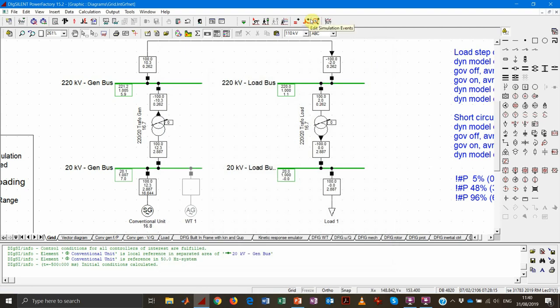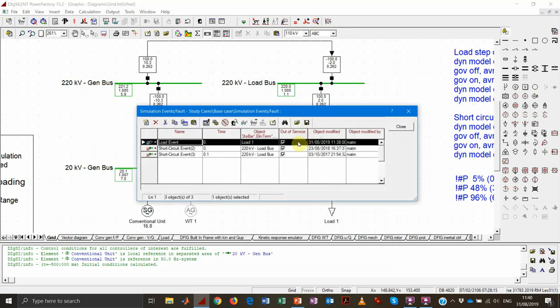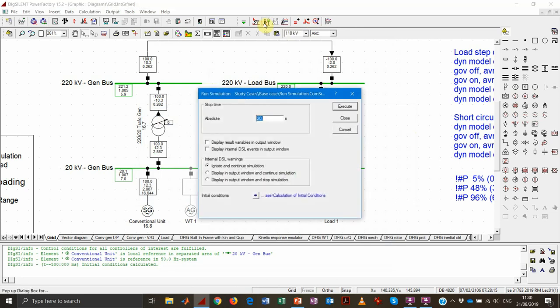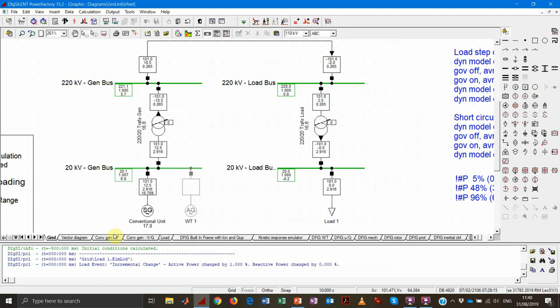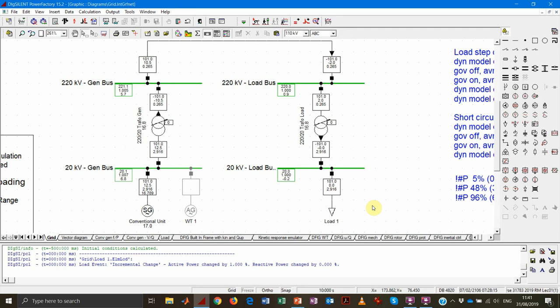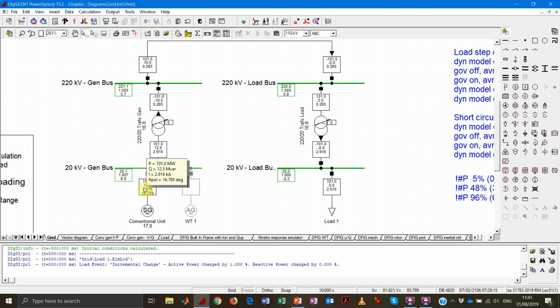Now let's initialize the simulation, put our load event back in service, and run the analysis for 10 seconds. We can see that something happened in the system. Looking at the end-of-simulation layout, the load increased its power consumption by 1 megawatt — now 101 megawatts — as expected. The generator also increased its production by 1 megawatt.